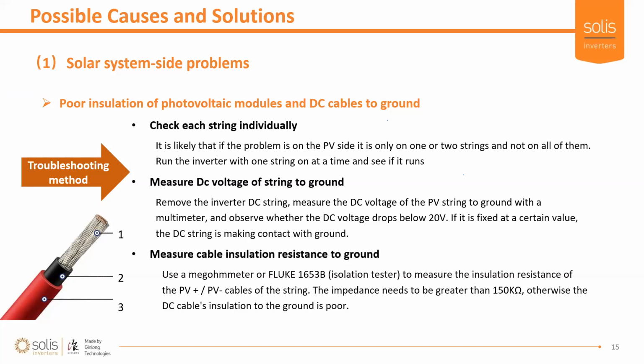Then finally, the solution: if you have a nice expensive isolation tester, then you can use that to measure the insulation resistance. Please note that if you do use this, make sure that you have your earth connection or your earth probe plugged in. Having it floating is useless. It won't get you a result. You will always find high resistance and you're basically doing nothing.